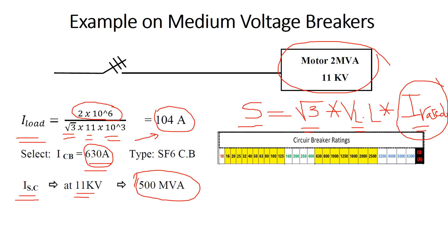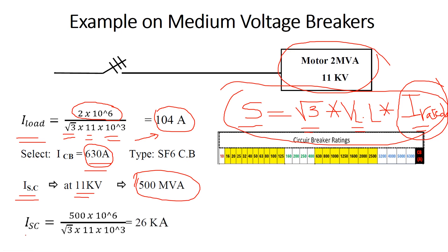Using the formula S_sc = √3 × V_LL × I_sc, we get: I_sc = 500 MVA / (√3 × 11 kV) = 26 kA. So we need a circuit breaker rated at 630 A that can withstand 11 kV and a short circuit current of 26 kA.